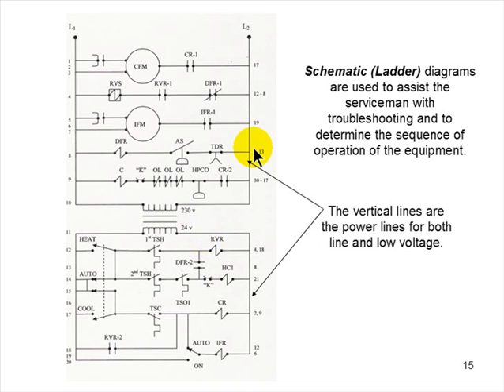Know that the vertical lines, if the schematic is in this position, or the horizontal lines if it's turned sideways, represent power. Here's the line voltage, L1, L2. This is 240 volts, 110 to ground, 110 to ground. Here's the induced secondary current, 24, 24. It's not grounded, so this is one side of 24 induced, this is the other side of 24. It's not going to be 24 to ground because there is no ground. But know that the vertical lines in this case are power sources.